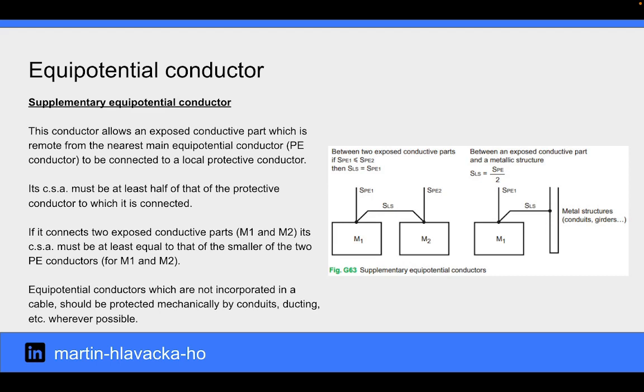A supplementary equipotential conductor allows an exposed conductive part that is remote from the nearest main equipotential conductor to be connected to a local protective conductor. Its CSA must be at least half of that of the protective conductor to which it is connected. If it connects two exposed conductive parts, its CSA must be at least equal to that of the smaller of the two PE conductors.